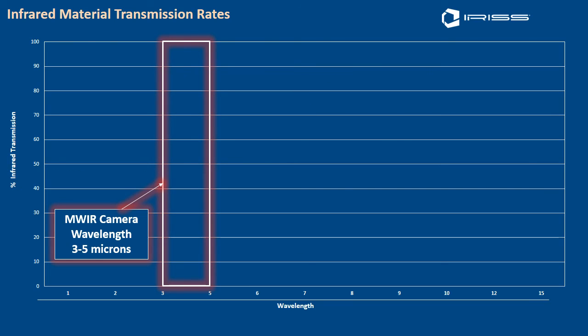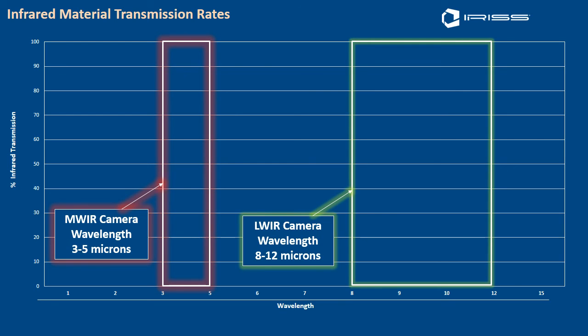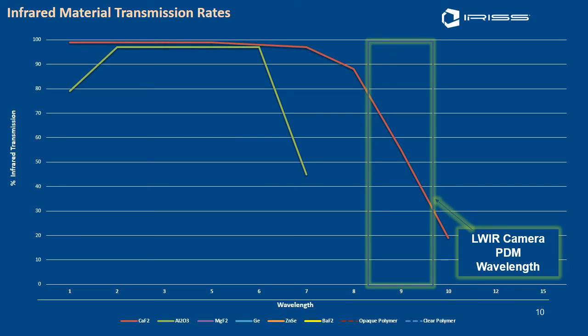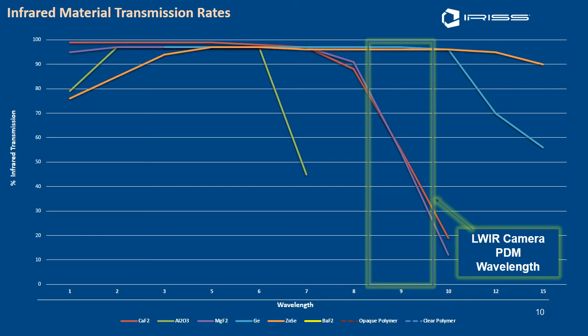There are two wavelengths primarily utilized in today's infrared industry: the mid-wavelength which is 3 to 5 microns, and the long wavelength which is 8 to 12 microns — where 99% of the equipment operates, and most likely the camera you're using is a long wave infrared camera. Looking at the PDM wavelength of 8.5 to 9.5 microns, we can see where different material transmissions fall. The materials include: calcium fluoride, sapphire, magnesium fluoride, germanium — the material your camera lens is made from — zinc selenide, barium fluoride, opaque polymers, and clear polymers.